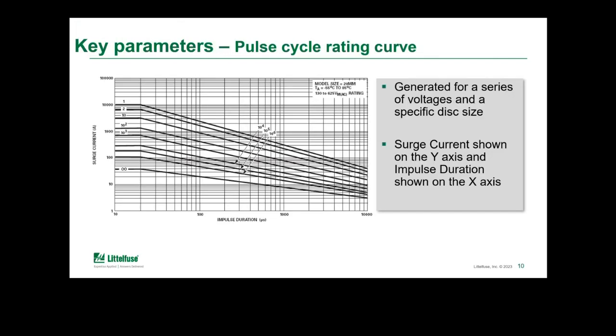Another key characteristic of MOVs is this pulse cycle limit, and this is represented by pulse cycle capability curves, all of which are located on the data sheet. Each curve typically represents a family and a size within a series of MOVs. So if we look at this curve, we see that for this particular one at 10,000 amps, it can handle a single pulse, one time, at 10,000 amps for a 20 microsecond waveform. So that relates back to that 8 by 20 microsecond.